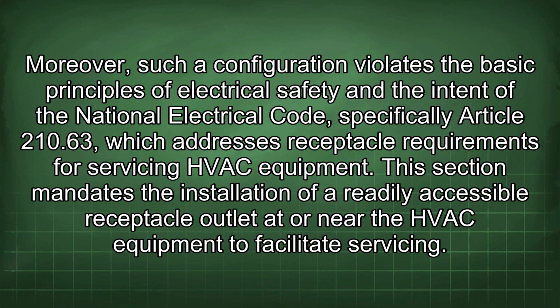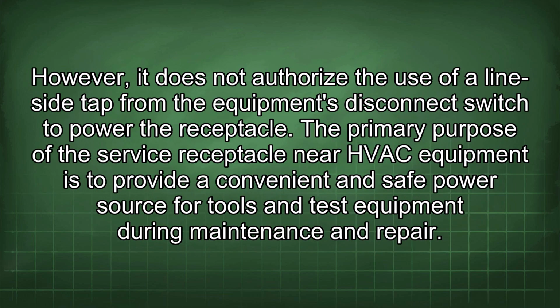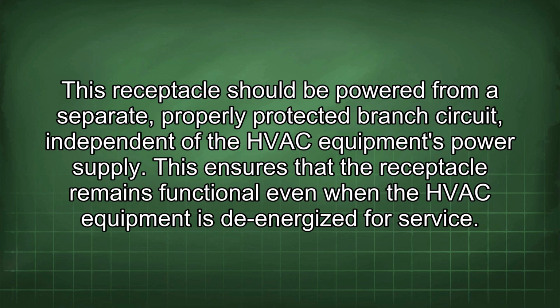This section mandates the installation of a readily accessible receptacle outlet at or near the HVAC equipment to facilitate servicing. However, it does not authorize the use of a line-side tap from the equipment's disconnect switch to power the receptacle. The primary purpose of the service receptacle near HVAC equipment is to provide a convenient and safe power source for tools and test equipment during maintenance and repair. This receptacle should be powered from a separate, properly protected branch circuit, independent of the HVAC equipment's power supply. This ensures that the receptacle remains functional even when the HVAC equipment is de-energized for service.